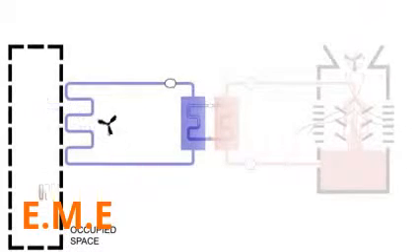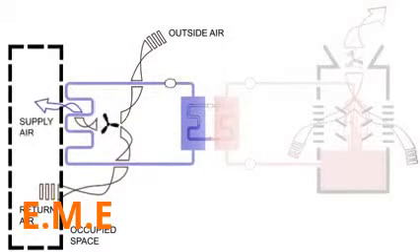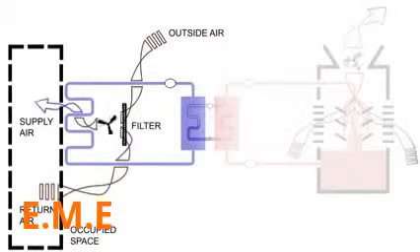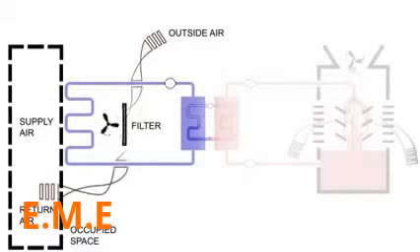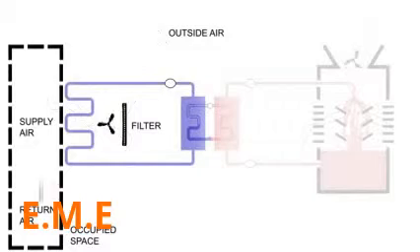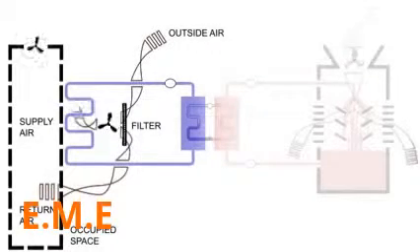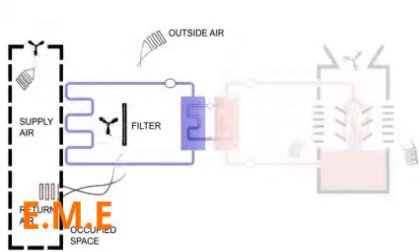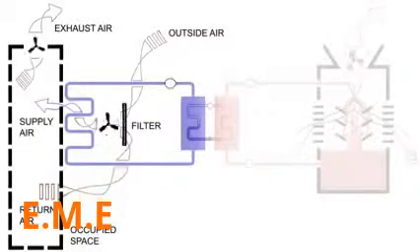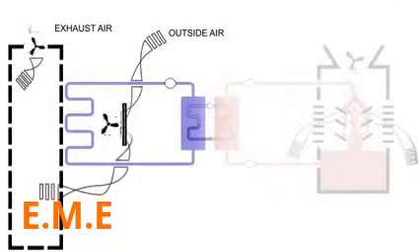Outside air is introduced into the air loop, and that outside air combines with recirculated air from the room before both volumes of air move across the filter. Of course, simply adding lots of outside air without exhausting some of the inside air is not stable. So exhaust fans release some of the portion of the stale interior air, that portion not destined for recirculation, to the outdoors.